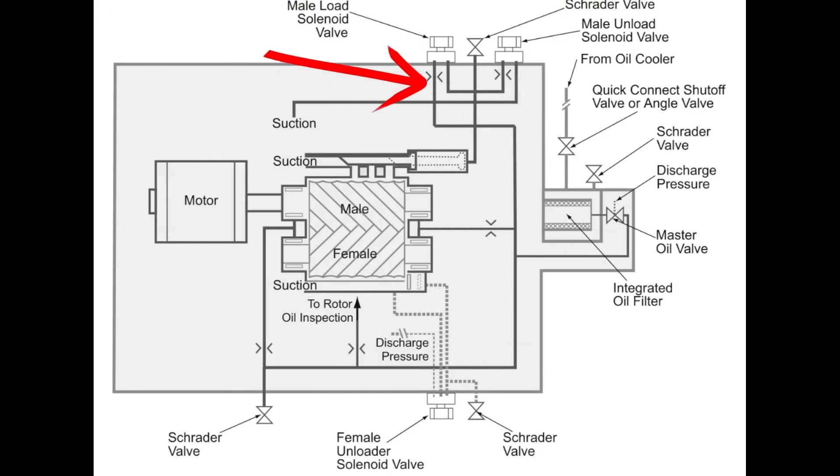Then these will begin to do their job. And then at shutdown, the unload solenoid gets hard activated and we are going to go through a full unload process when the compressor goes to shut down.